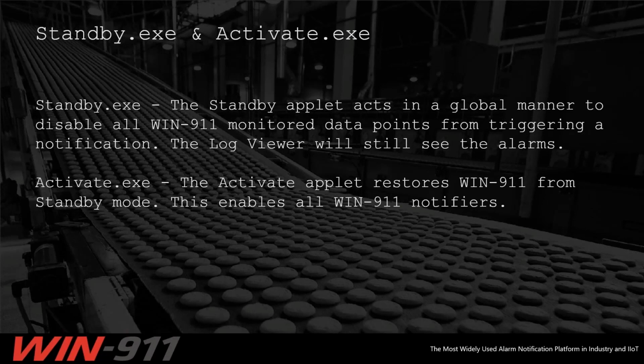So the Standby and Activate executables. Standby.exe is the applet that acts in a global manner, disables all WIN-911 monitoring data points from triggering. And you're not going to get any notifications. Everything is still going to kind of be running in the background. Log viewer will still see the alarms, but the notification from dispatcher sending that out to a notification method is not going to happen. So it is still running. Services are on. Log viewer is going to see it, but in standby mode, you're not going to be sent notifications.